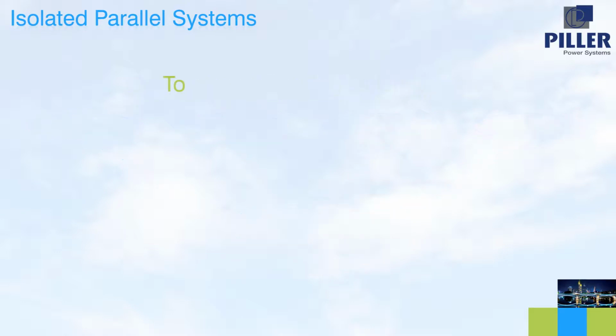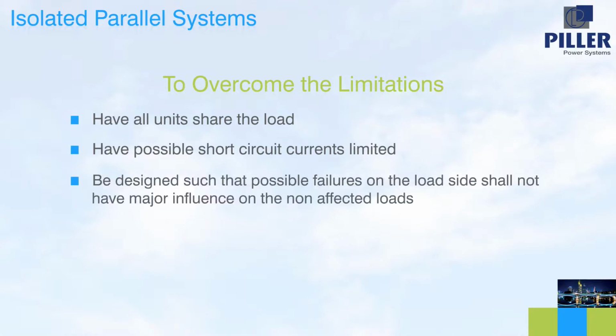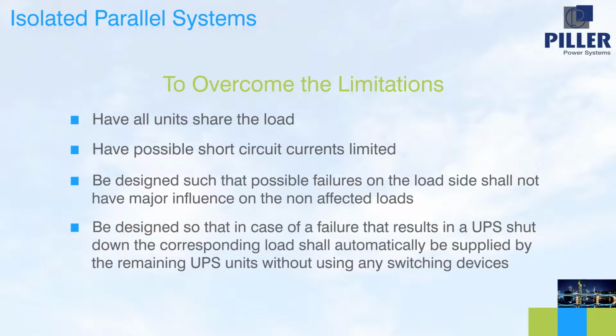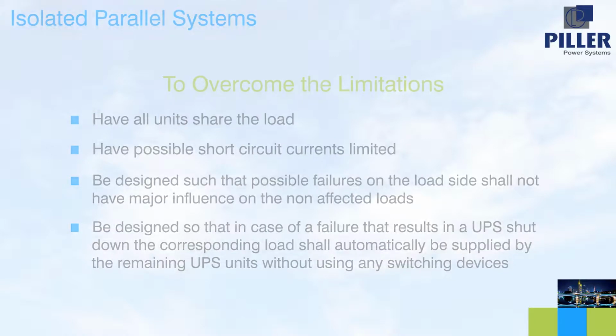A solution that could overcome these limitations would need to have all the units share the load, have possible short-circuit currents limited, be designed such that possible failures on the load side shall not have a major influence on the non-affected loads, and be designed so that in case of failure that results in a UPS shutdown, the corresponding load shall automatically be supplied by the remaining UPS units without using any switching devices. That solution is known as isolated parallel.